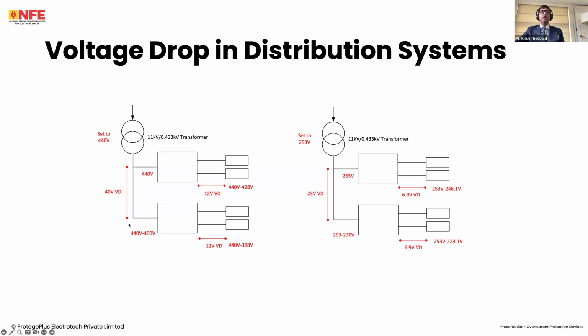I design the circuit such that I get the nominal value, 400 volts, at the most extreme point of commencement of supply. So remember, what I'm doing is designing for the furthest point of commencement of supply such that once the transformer is set to the highest value, taking into account the tolerance, so 400 volt plus 10%, I am getting 400 volts here. Same case here, 253 is the highest value I can go to, taking into account a 10% tolerance, and I want 230 here. So I design this circuit such that I get a 10% volt drop in the actual distribution circuit, the distribution system.